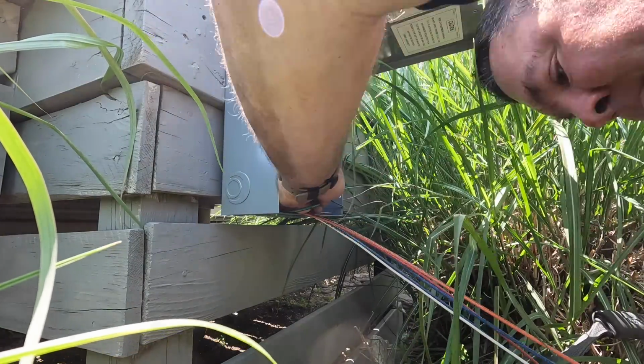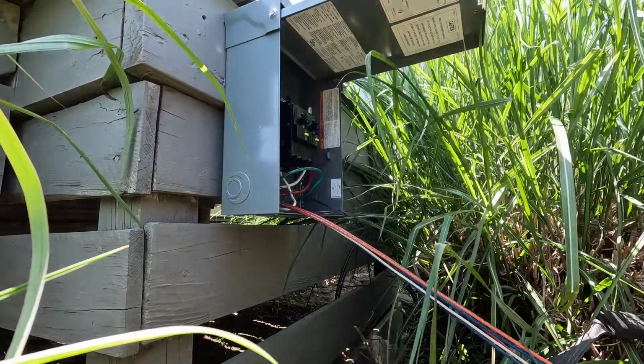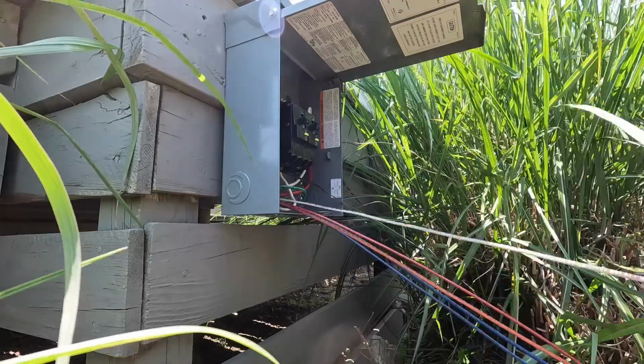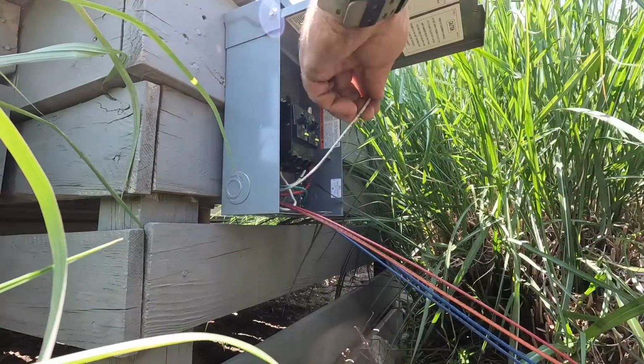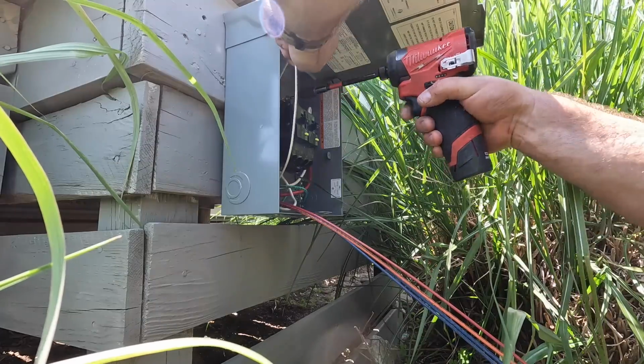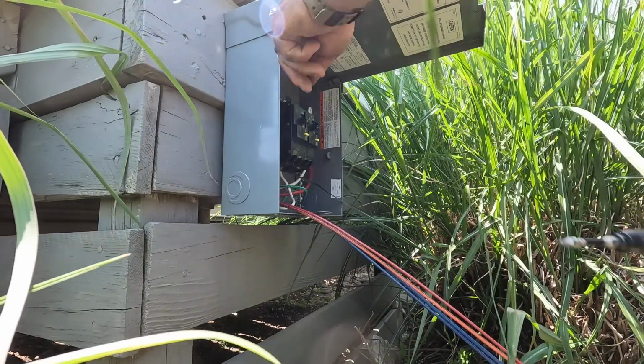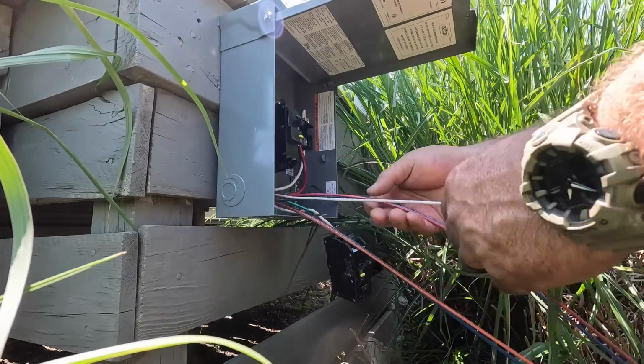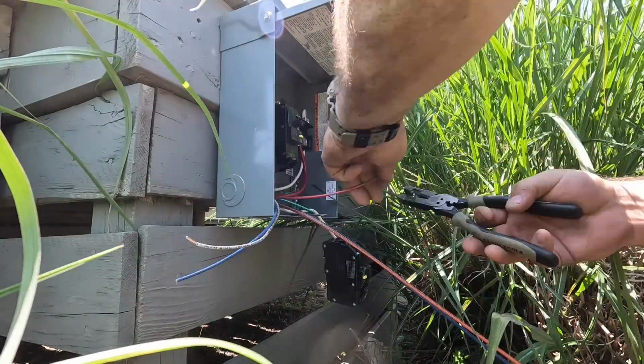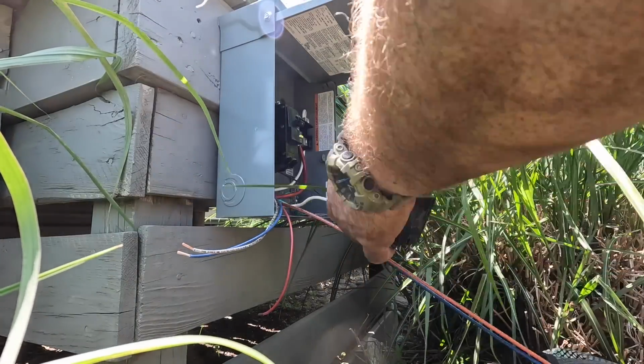So once the hot tub has been wired, I'm coming back here and I'm hooking up my circuit breakers. So with a GFCI breaker, you don't need to have a neutral connected to the GFCI breaker for it to work properly. But you do need to hook up the tail that comes from the GFCI breaker to the neutral bar.